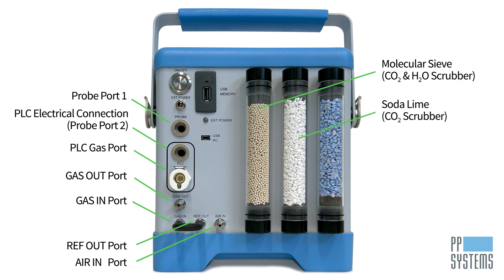An external air filter is included to attach to the air in port in dirty or dusty environments. There are three absorber columns used by the Targus One. The AutoZero column contains molecular sieve, a CO2 and H2O scrubbing desiccant, that removes all CO2 and H2O from the airstream. The next column contains the CO2 scrubber soda lime for CO2 control, and the other contains the H2O scrubber Drierite for H2O control.